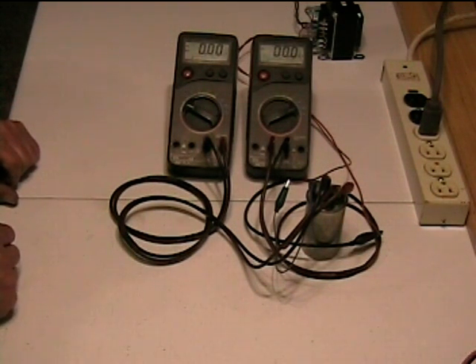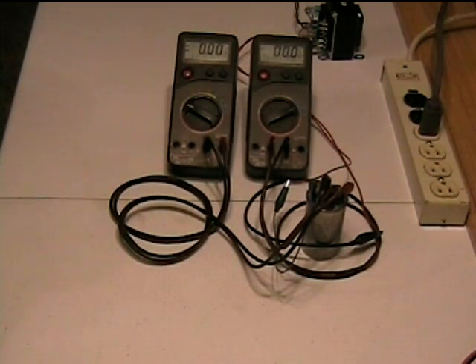Now if the readings come out low, you know you have a bad capacitor. Plus or minus 10% is not a big deal. In the larger capacitors, like a motor starting capacitor, like you might have on a compressor or a pump, which are going to be 300 or 400 microfarads or more, the tolerances are much greater. It might be 20% give or take, which would be acceptable for that. But if the motor is unable to start and the capacitor reads a little low, you may need to replace it. But other than that, it's really pretty simple.